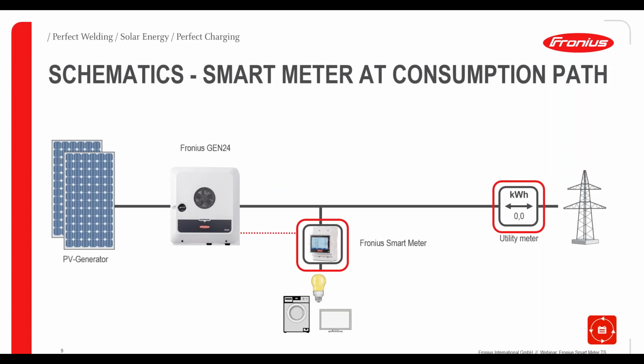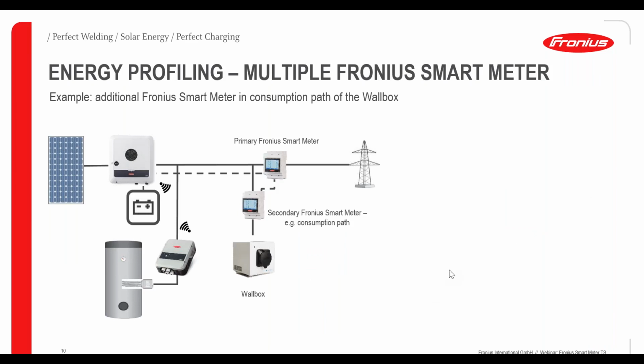The second option is to install the smart meter in the consumption path of the load. As said, it's more recommended to put it in the feeding point, but it is also possible to put it in the consumption path of the load. Then we have the third alternative, when we have energy profiling and more than one smart meter in a system. We have the primary smart meter in the feeding point, and a secondary smart meter in the consumption path of the specific load. Here we have a complete PV system with our Gen 24 hybrid inverter connected to a battery. We even have an Ohmpilot for hot water generation and the wall box for EV charging. Then we have put the secondary smart meter at the consumption path of the wall box to know the exact consumption of this specific consumer, which is the electric vehicle.